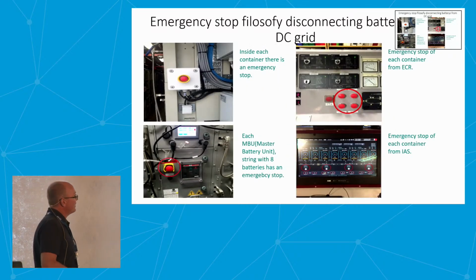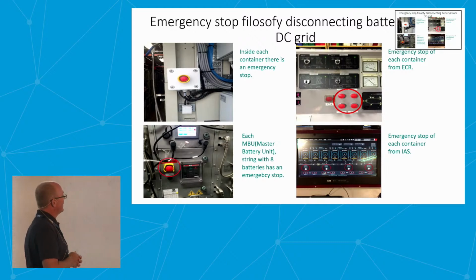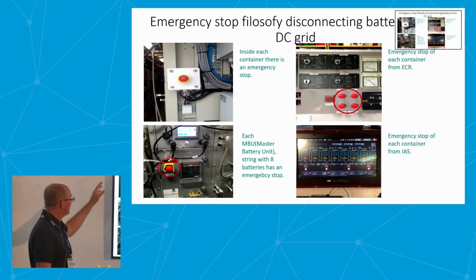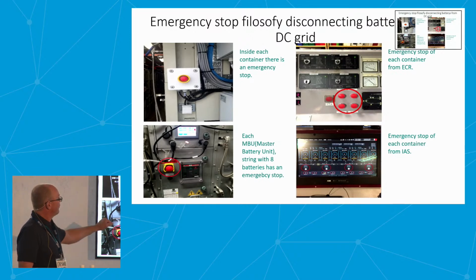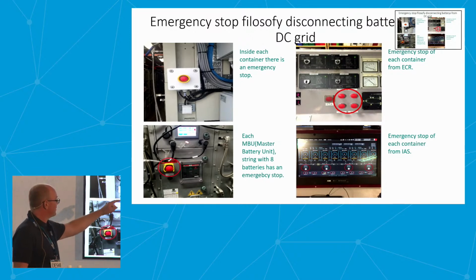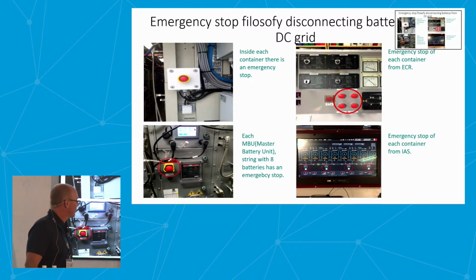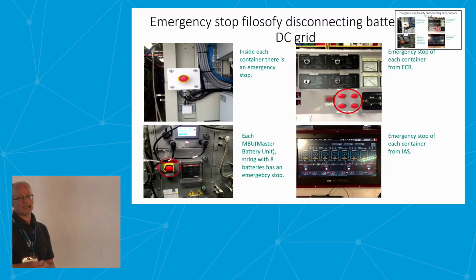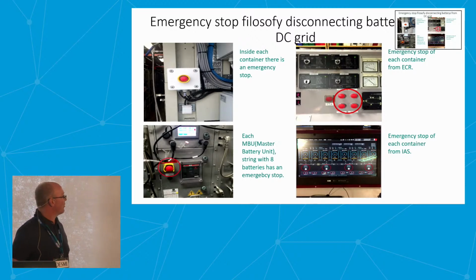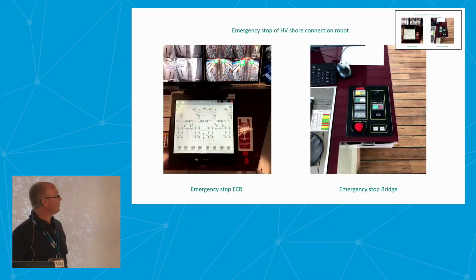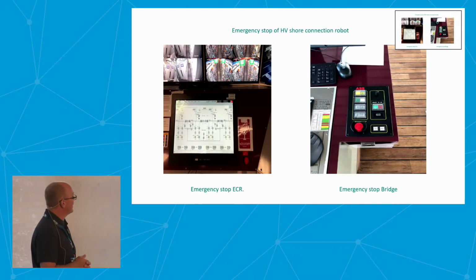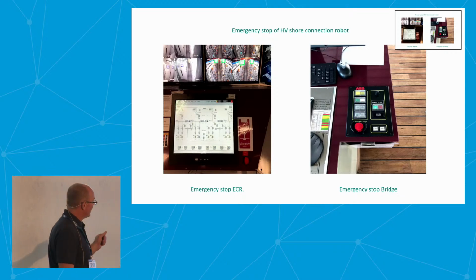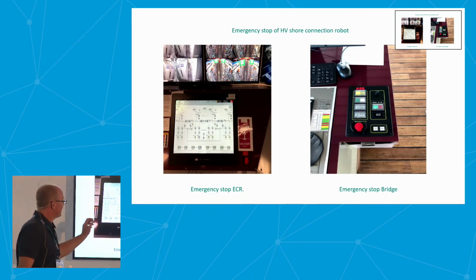Emergency stop philosophy is also something that we discussed a lot during the risk assessment in the early stage of the planning of the system, and there are a lot of emergency stops. We have them inside the containers, locally at the strings. You can do it from the control room, ECR, and you can also do it from the integrated automation system. Things can change really quickly with this amount of enclosed energy, so we think this is very important. Also, with the high voltage shore connection robot, we can emergency stop it very quickly in the ECR or on the bridge.